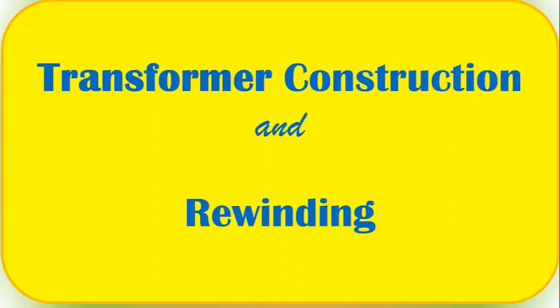Transformer construction and rewinding. A new transformer is wound similarly to one that is being repaired or rewound. However, in a new transformer, the number of turns and the sizes of wires and cores are calculated according to its specification. A coil is unwound on a winding machine to determine the number of turns in the original coil as registered in the counter of the machine.